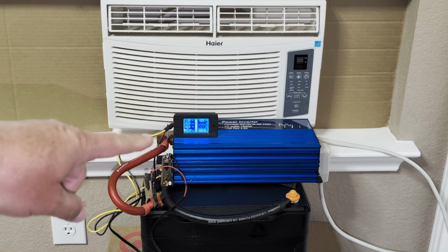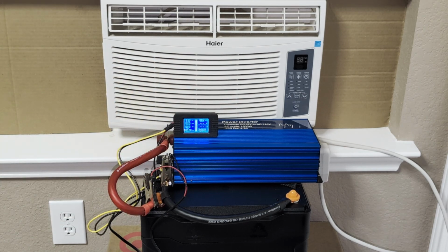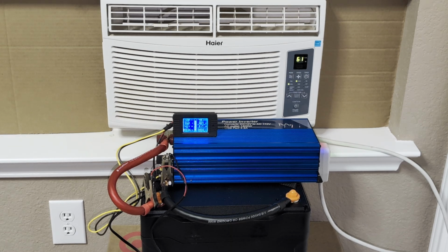So I'm going to turn on the inverter, which should kick off this whole process. The inverter's turned on, now I'm turning on the AC unit. When I kicked it on, that inrush of power happened as the motor kicked off, and it handled that with no problem. Now it's going to be pulling about 500 to 600 watts on a mostly constant basis because it's pretty hot outside and I've got that thing turned all the way down. We're going to see just how many watt hours we get out of this battery. I'll come back when it's empty.